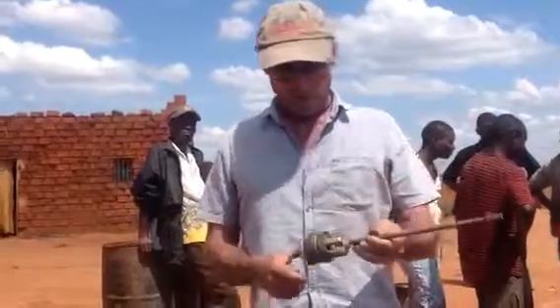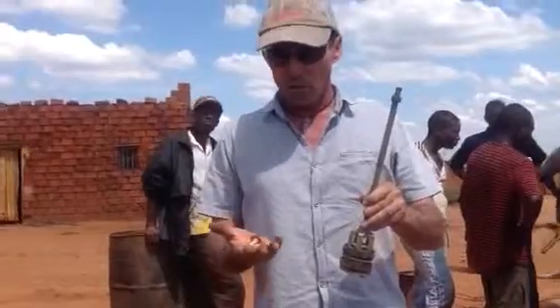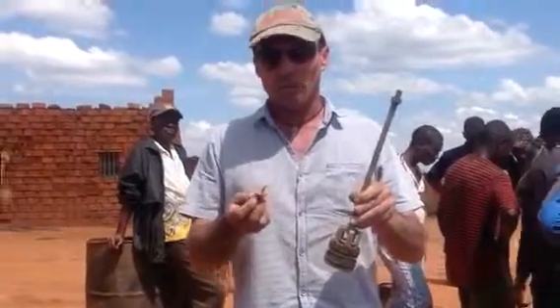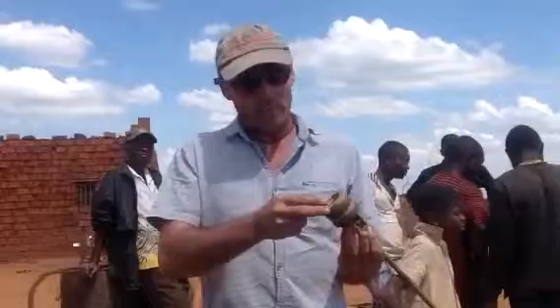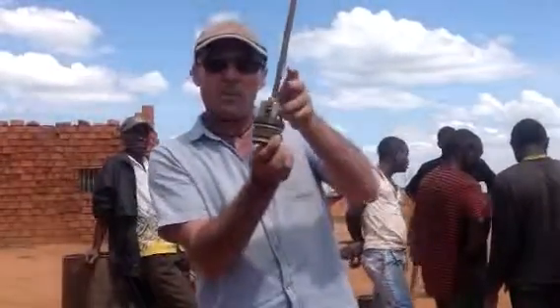We removed the pump and found the problem — it's just a non-return valve that's broken inside. It's a simple $1 or $2 part. There it is there. That was jamming the pump, broken inside, and it was stopping the seal from going up and down.